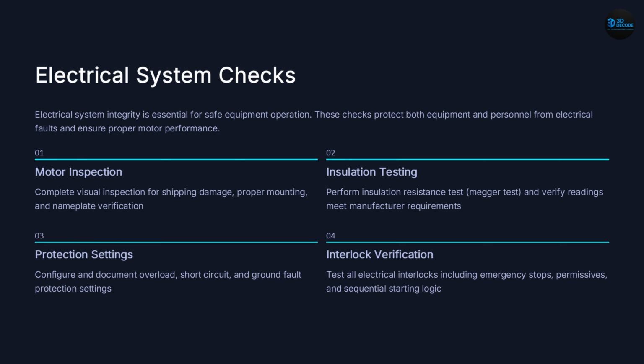Now let's move into the electrical side. Even the best pump means nothing if the motor can't operate safely. The first step is motor inspection. Check for shipping damage, verify mounting integrity, confirm nameplate data. Then perform insulation testing. The Megger test verifies motor insulation health, and this simple test can prevent expensive electrical failures. Next comes protection settings: overload protection, short circuit protection, ground fault protection, all properly configured. And finally, interlock verification. Emergency stops, permissives, starting logic, shutdown logic. Everything must work exactly as designed.